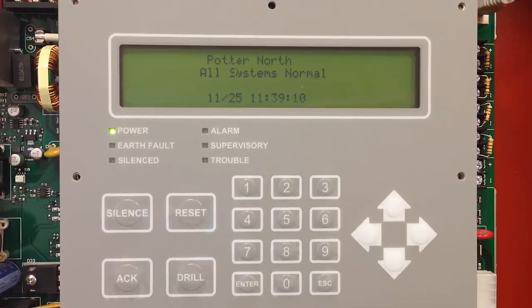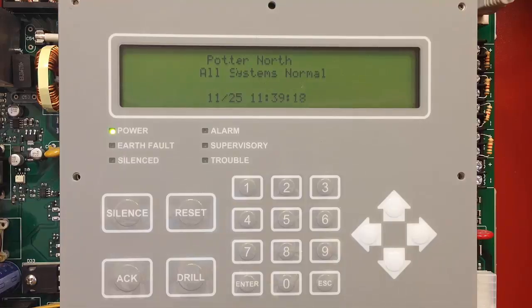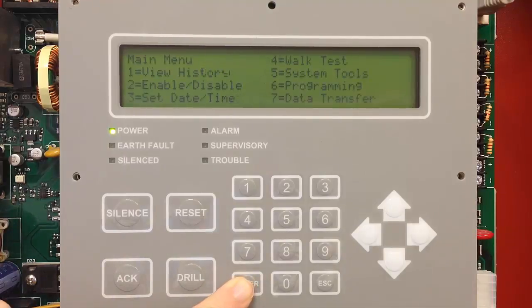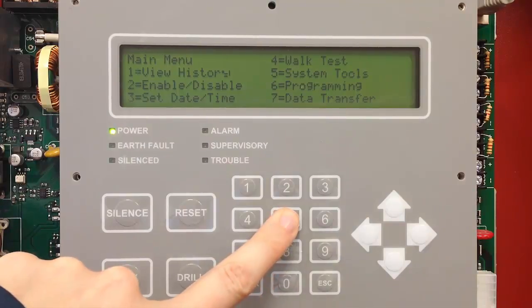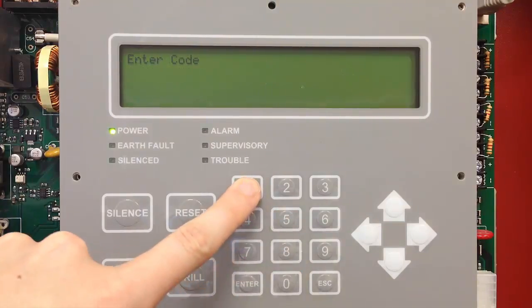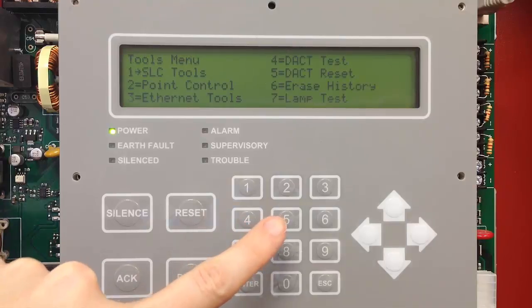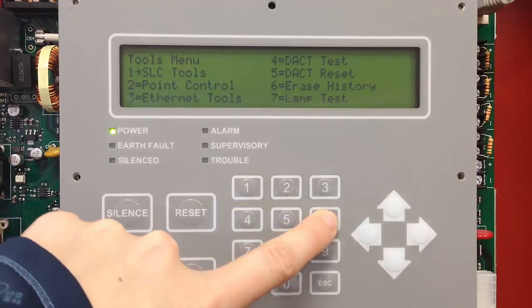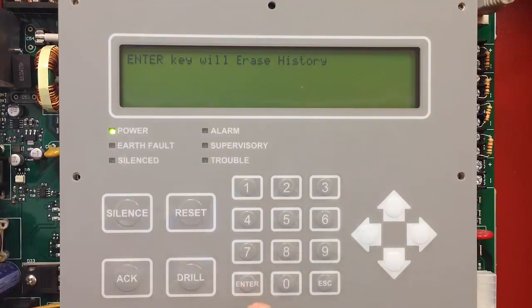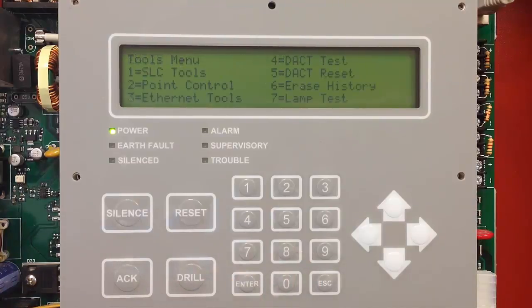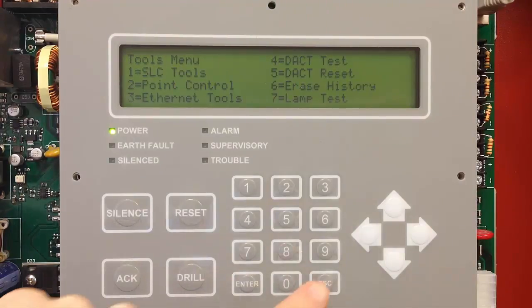The next step would be to clear the panel history. This allows the test events to be the only events in the panel history, creating a clean test report in the end. To clear the panel history, access the main menu by pressing enter, then choose number 5 for system tools, enter the code, and then select number 6, erase history. Press the enter key to erase history, and now the panel history has been erased.